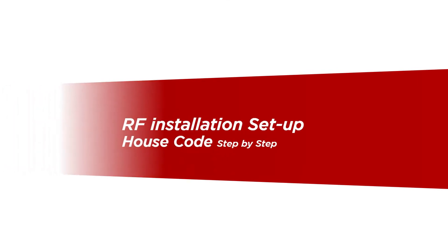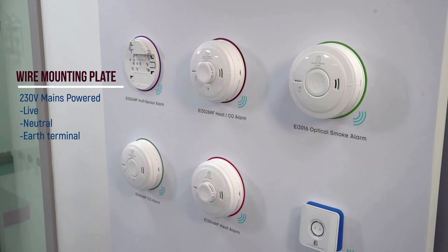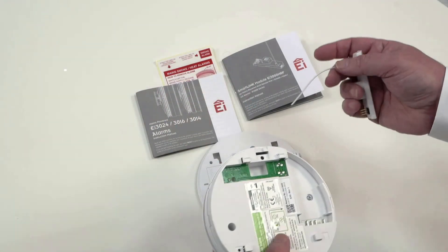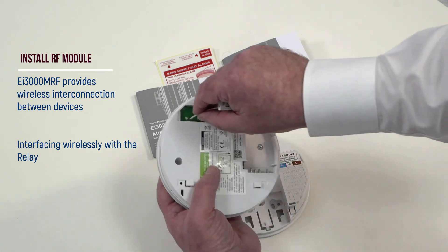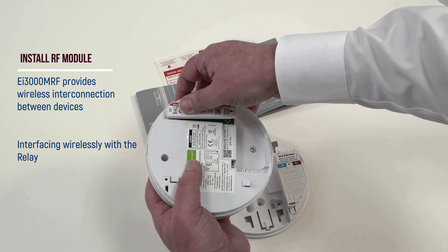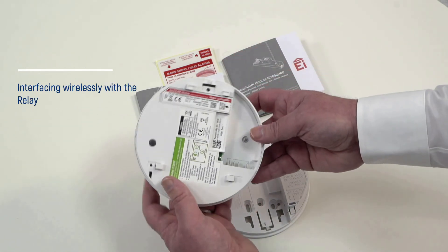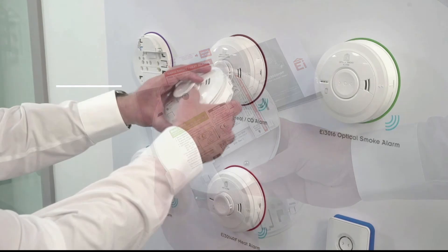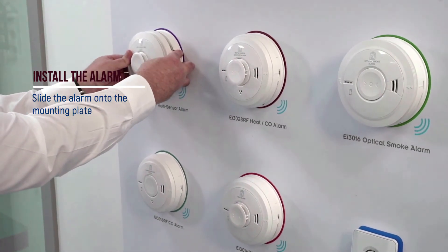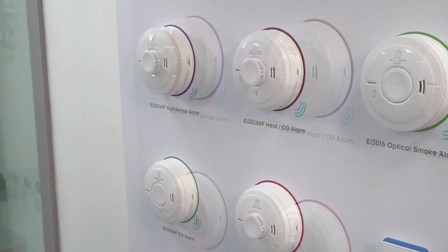Wireless setup is quick and easy. For mains powered alarms, wire the 230-volt mains powered mounting plates. Insert the EI 3000 MRF wireless module. Feed the antenna into its guide through the aperture. Line up the module pins with the receptor socket and gently push the module into the base of the alarm. Slide the alarm onto the mounting plate and you will hear a click to indicate the alarm has docked correctly.